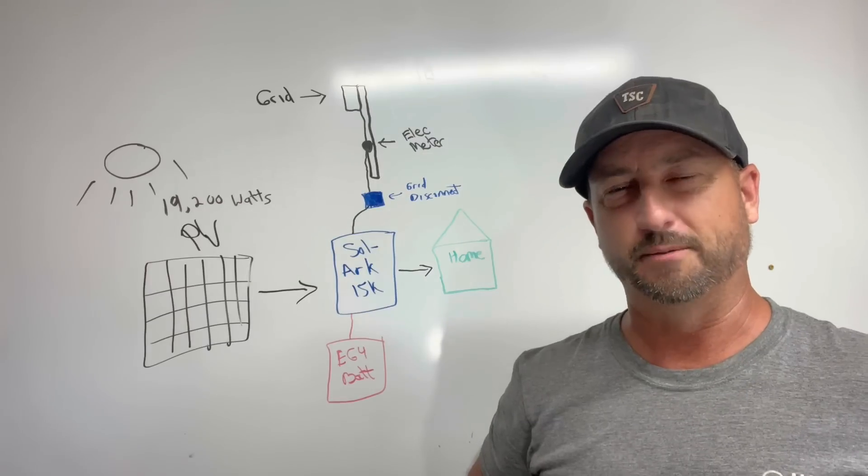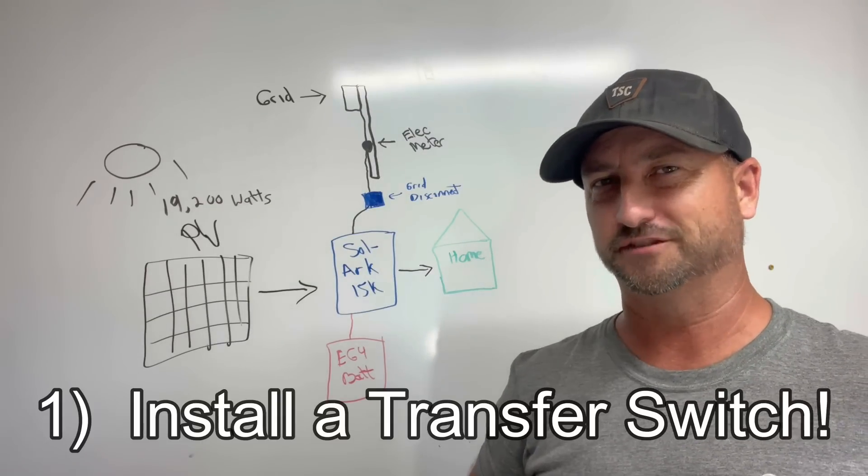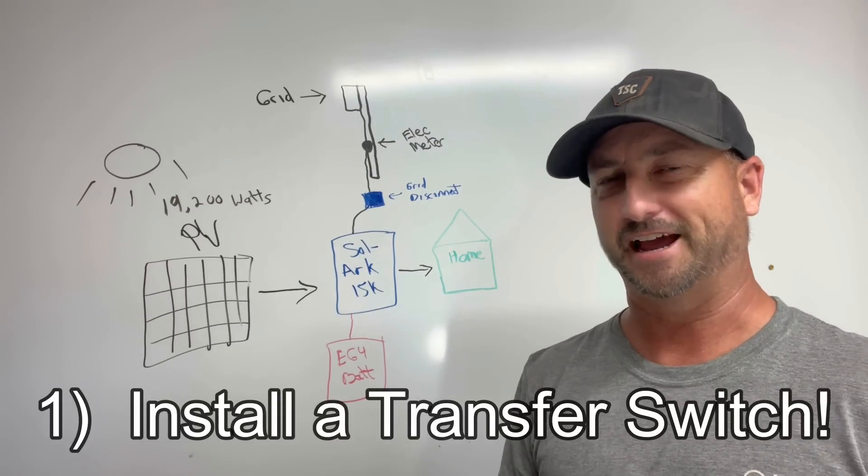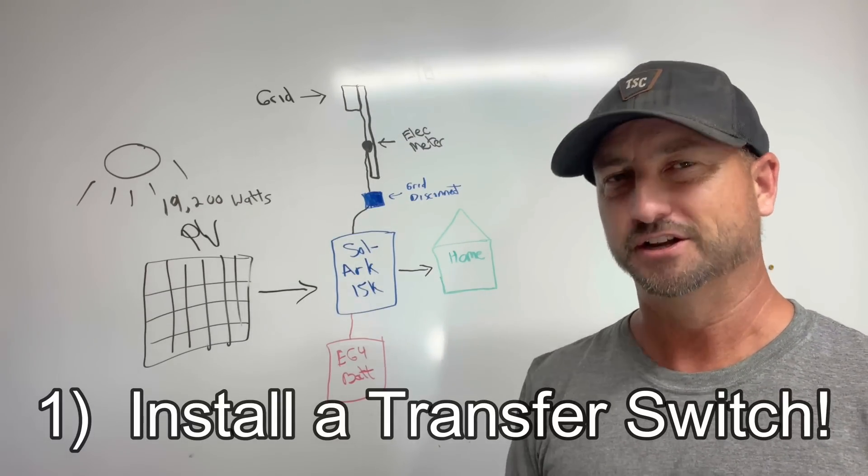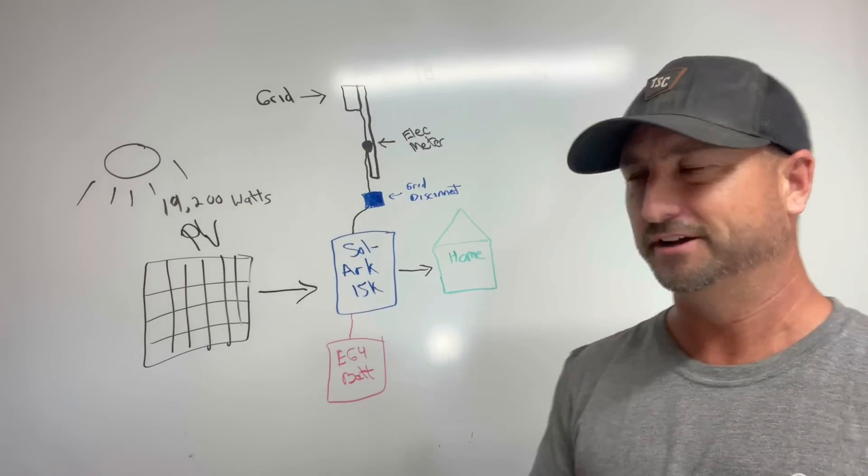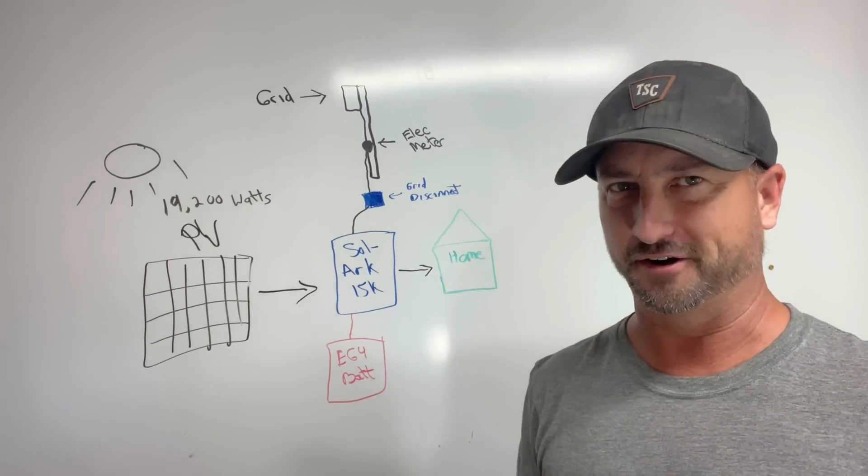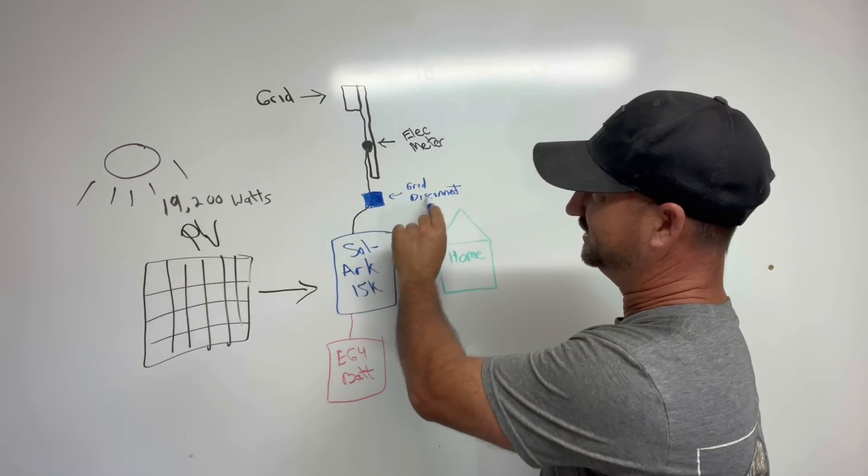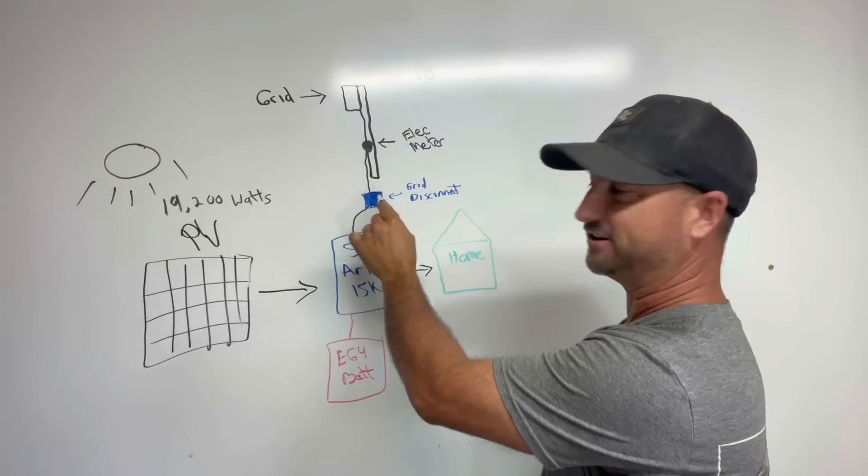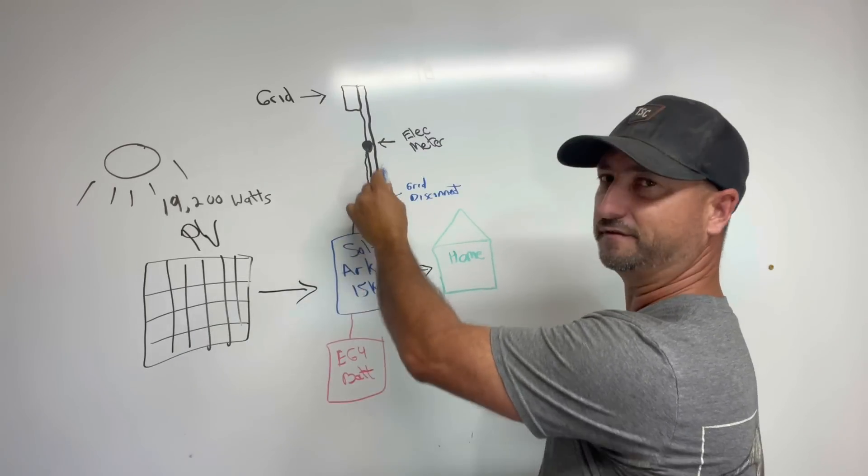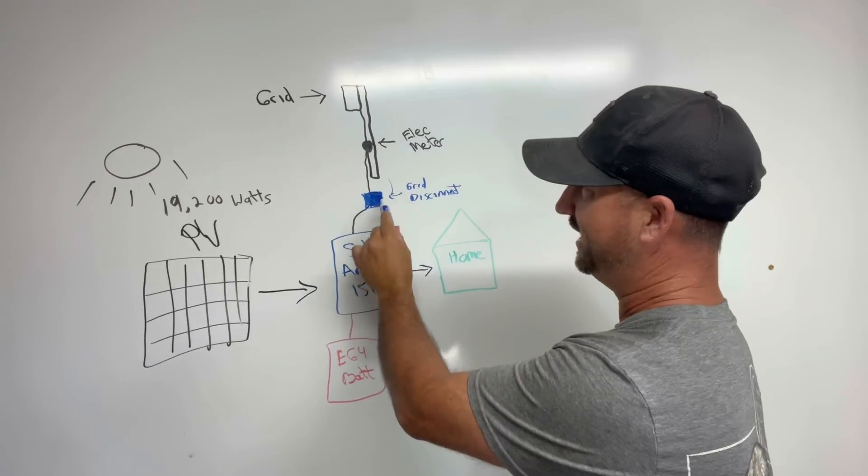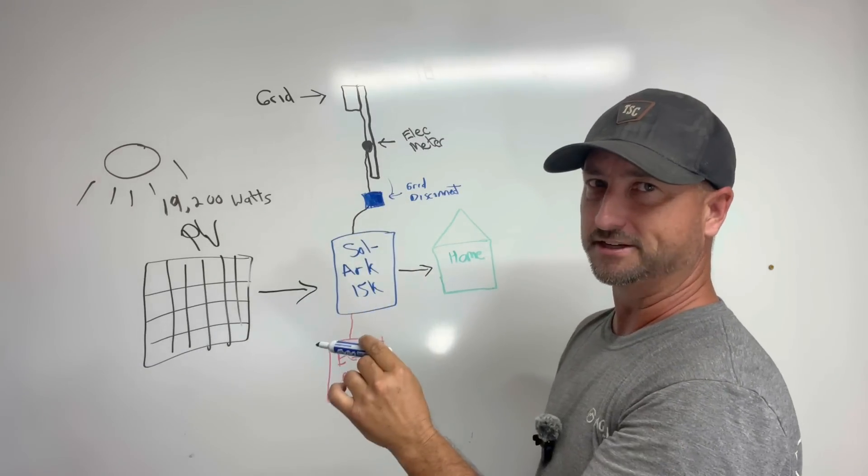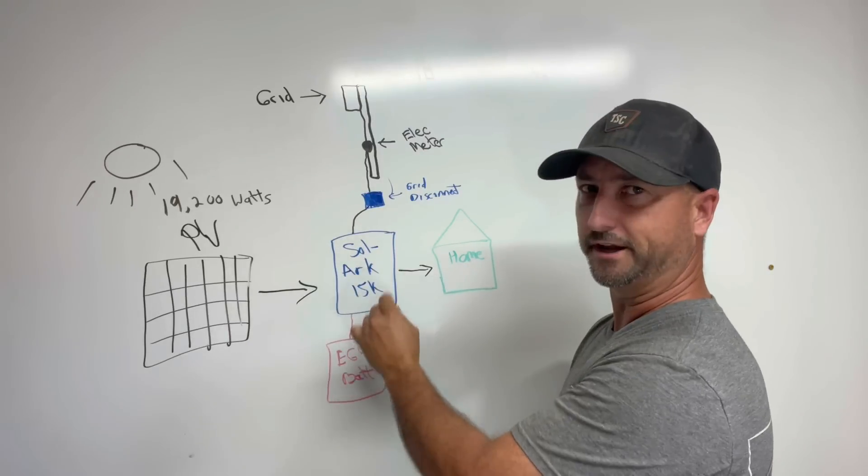So number one, the first thing I would change if I had to do it all over again is add a transfer switch. So right now really all the code requires at least in my area is a disconnect. You can connect your system, disconnect it from the grid so there's no chance of feeding back to the grid. I just put in a disconnect but what that means is when I need to do a firmware update on the Solark, which isn't often, but it is oftentimes I want to add something, test out different products, add more batteries, add more panels.